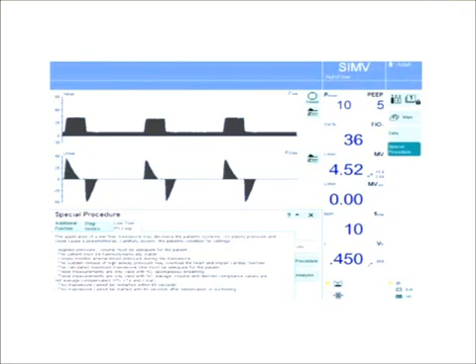So this slide is an example of a Dräger Evita XL. To do the low flow maneuver or the static PV loop, you'll have to go into special procedures. So the special procedure key has been hit, and under special procedures there's a tab for low flow PV curve.